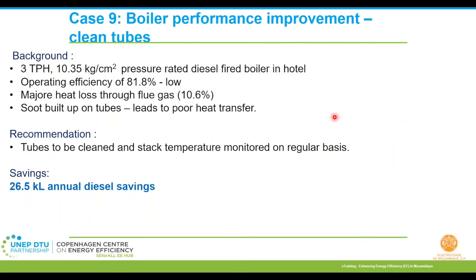Boiler performance improvements. Yes. So there was this again a hotel. I would say a 5-star hotel. It had a three tons per hour design and with 10.35 kg per centimeter square design pressure for a diesel fired boiler. We measured its operational efficiency, which was hardly about 81.8%.